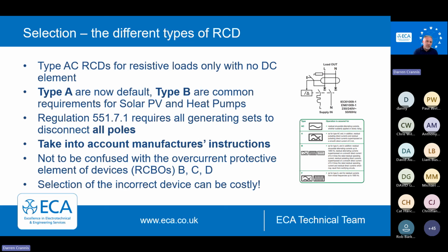We shouldn't confuse the type of RCD with the current time characteristics of the overcurrent device, so circuit breaker or fuse. Especially with circuit breakers, they are also called B, C, and Ds, and we have RCDs that also are called B, F, A, etc. So we've got to make sure that we get these right. I think if we were to go back through the standards many years ago, we probably wouldn't have chosen the letters to be similar. We probably would have chosen a different method.